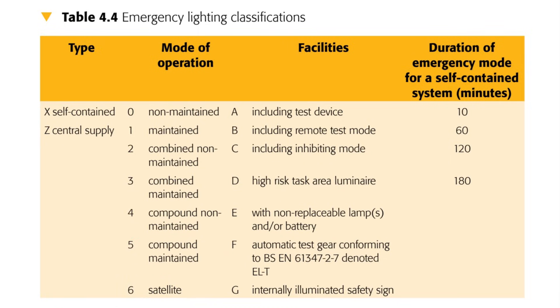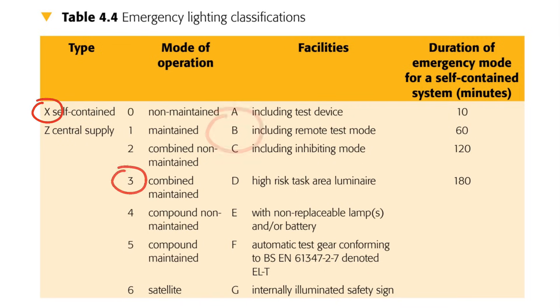One further thing to note about this table is that it's used to create codes that identify the characteristics of emergency lighting. So rather than reading each row from left to right — which could fool you into thinking that all self-contained non-maintained emergency lights include test devices and only need to last 10 minutes — each characteristic is selected by column and then combined to give a code that tells you information about the emergency light.